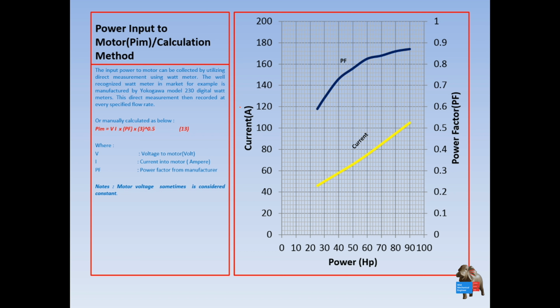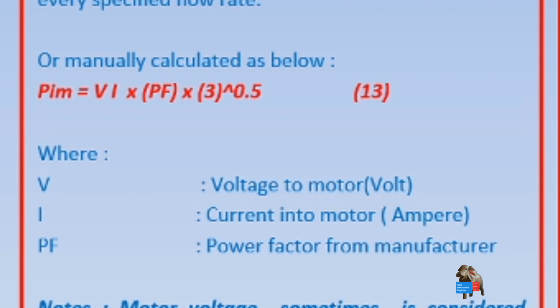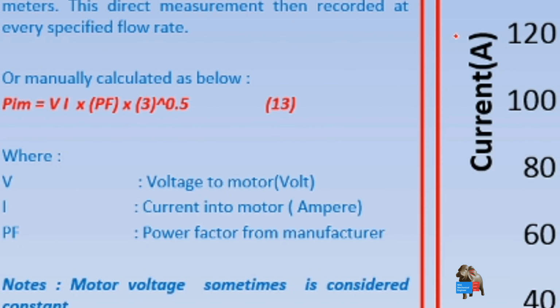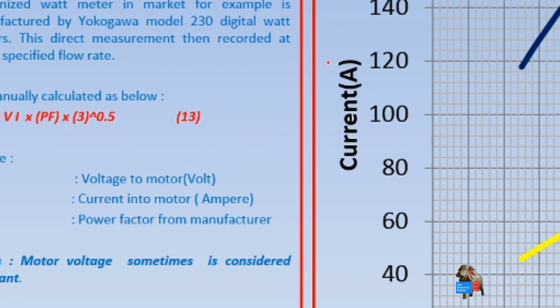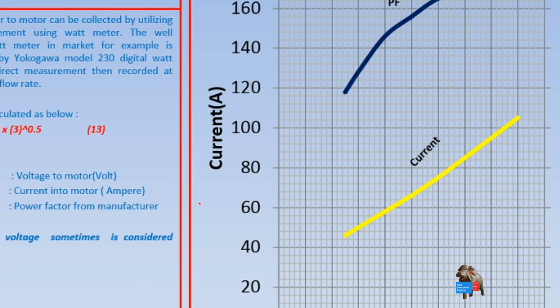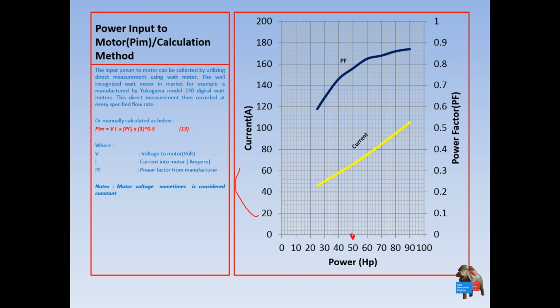And then you also need to calculate how much power actually goes into the motor during the testing at a specific flow capacity. You know that a motor has a graphical performance. The power generated, for example here, let's say 50 horsepower, at this current, record the current here, and then you have a power factor here.